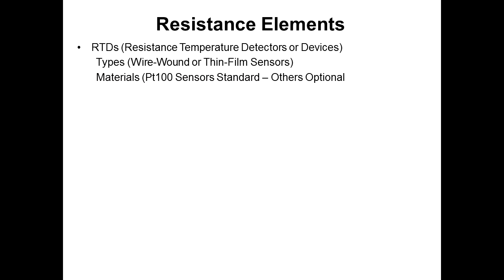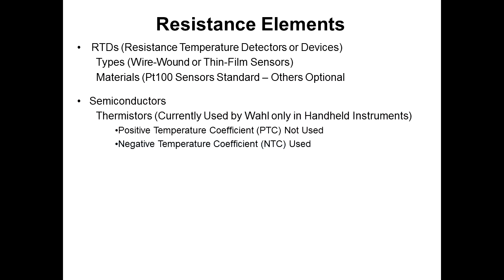Now we're going to go from thermocouples to resistance elements. RTDs, resistance temperature detectors, or devices. People use either term. There are wire wound and thin film sensors out there. PT100 is the most common. That's a 100 ohm platinum sensor, but there are others available. Then we have semiconductors, thermistors. We only build thermistors in handheld instruments. We have done some work on some specialized fixed instruments, but it's not in our standard product line.